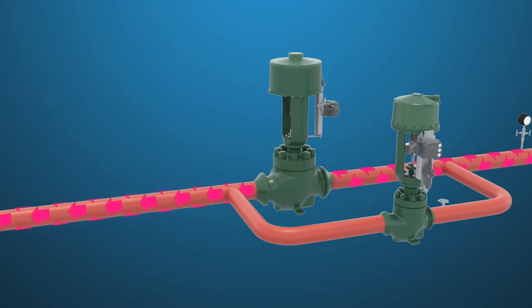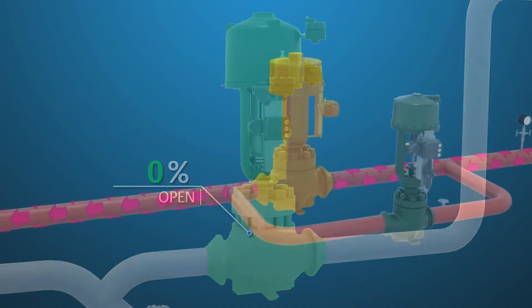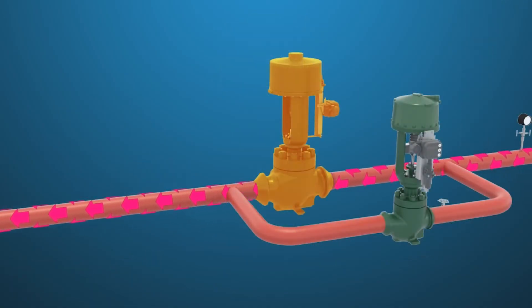Once the flow to the HRSG is more than or equal to 30% maximum continuous rating, the recirculation valve will go fully closed and operation will be on the main feed water valve. The plant is now in normal operating mode.